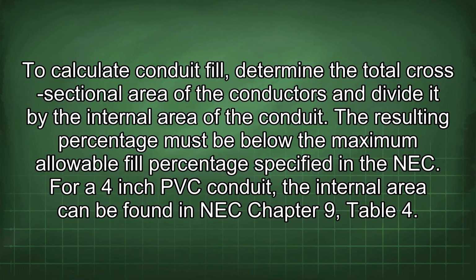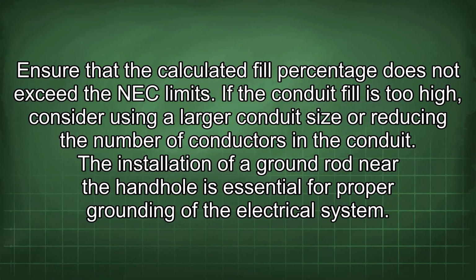To calculate conduit fill, determine the total cross-sectional area of the conductors and divide it by the internal area of the conduit. The resulting percentage must be below the maximum allowable fill percentage specified in the NEC. For a 4-inch PVC conduit, the internal area can be found in NEC Chapter 9, Table 4. Ensure that the calculated fill percentage does not exceed the NEC limits. If the conduit fill is too high, consider using a larger conduit size or reducing the number of conductors in the conduit. The installation of a ground rod near the handhole is essential for proper grounding of the electrical system.